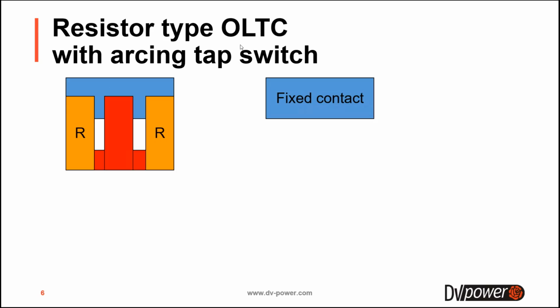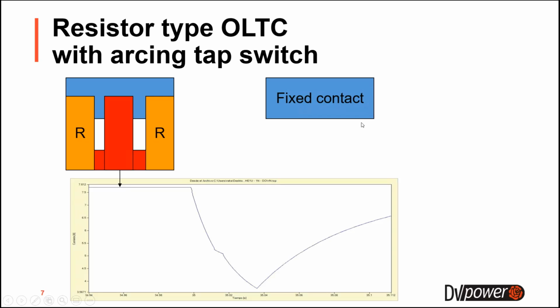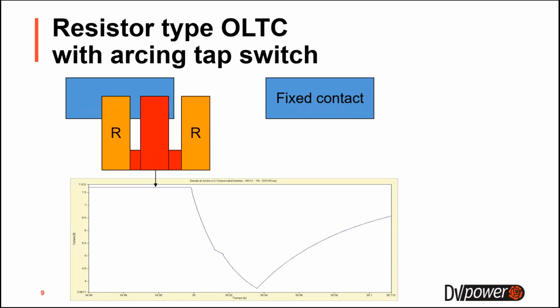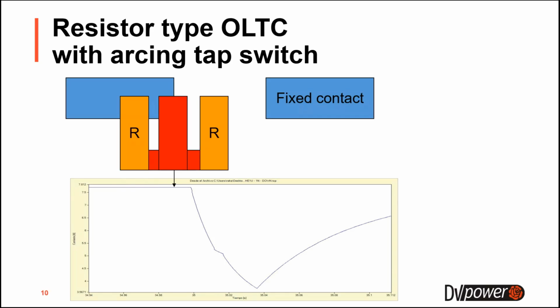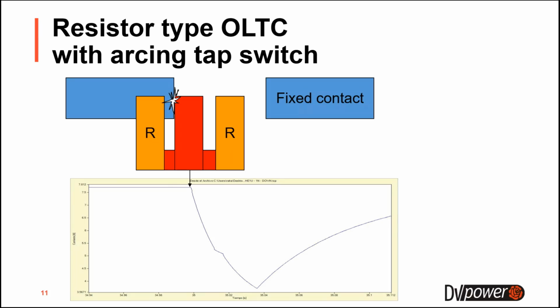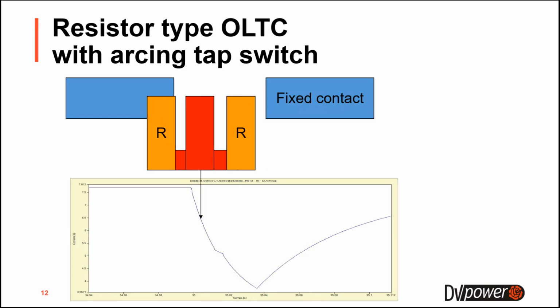So what we have here is two fixed or stationary contacts represented with the blue squares, and we have a simulation of an arcing tap switch with the two resistors in orange and the main current carrying contact represented with the red here. So a typical transition is that the moving contact will move. When the moving contact starts to move, we are still on this linear part of the DVtest graph, as you can see here. So the first characteristic point, or let's say the beginning of the transition, is the moment when the main current carrying contact separates from the stationary contact. In that moment, the current starts flowing through the transition resistor, and this is this part. This is where we have the drop of current, which is caused by introducing the transition resistor in the circuit.